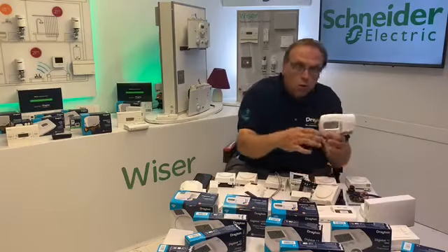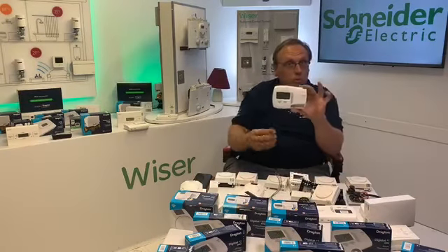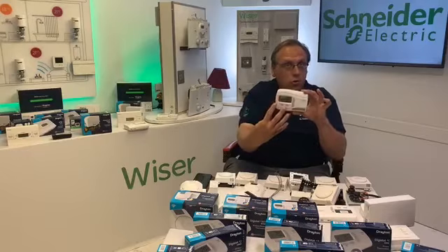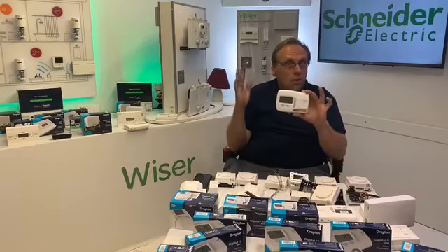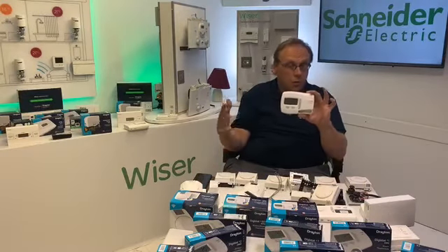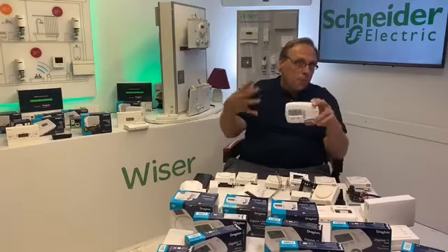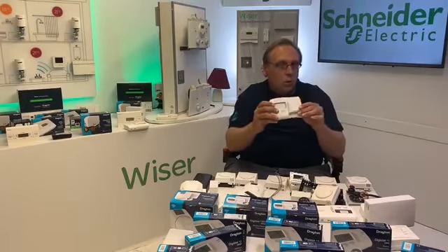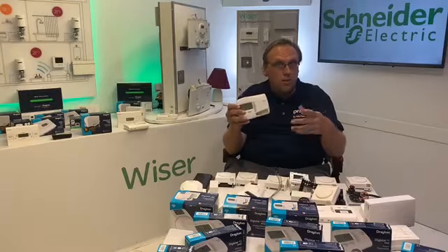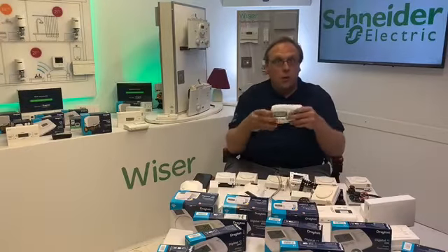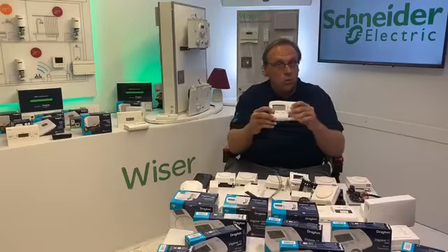The battery version, again, is a 2-wire thermostat. The battery is there to run the actual control, so all you need is a live in and a live out. And again, that is volt free. All of the Digistat range is volt free. It's just the mains one. Generally speaking, you'd use the battery if you were retrofitting, so you don't know what you're going to come up against, but you've got to have a live in and a live out, so you would use the battery.